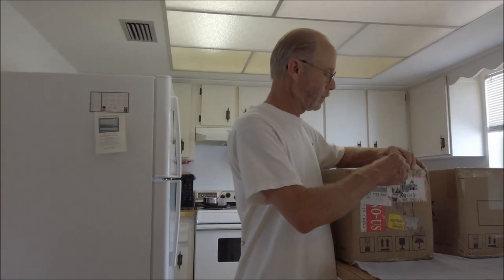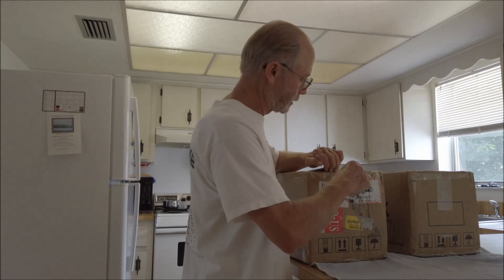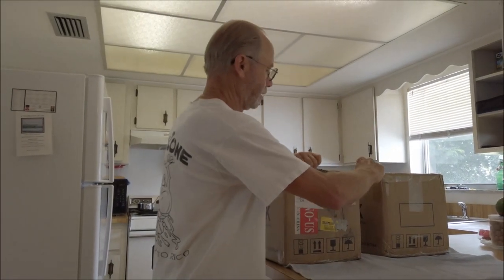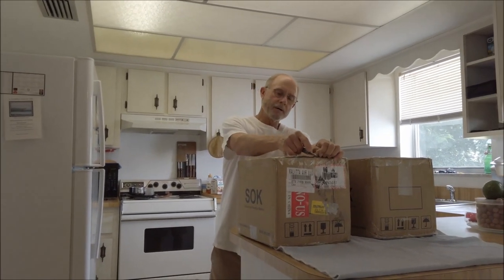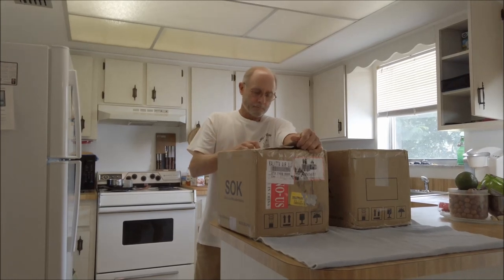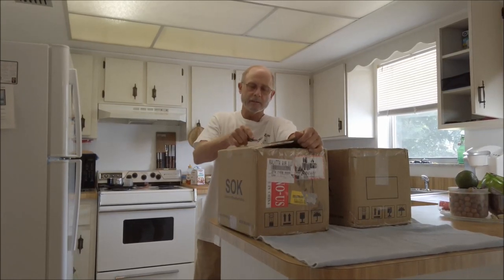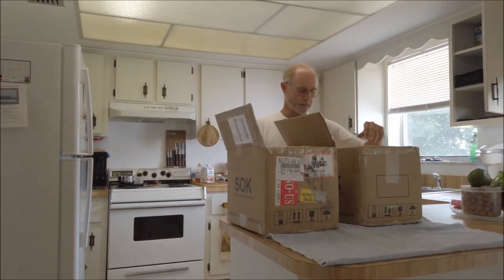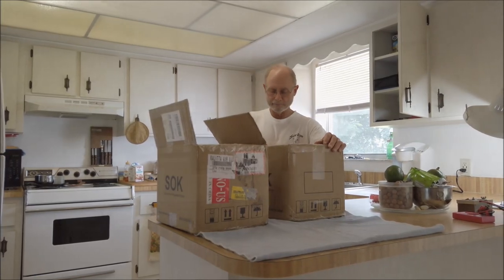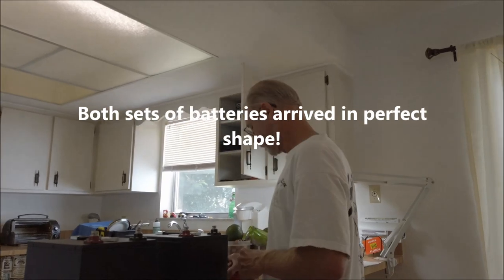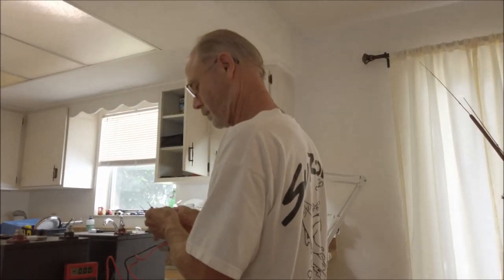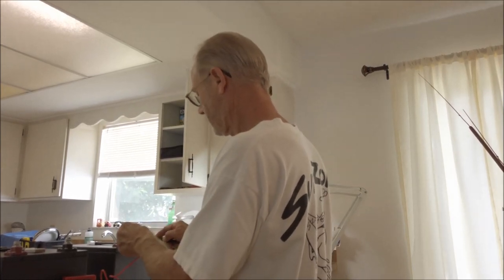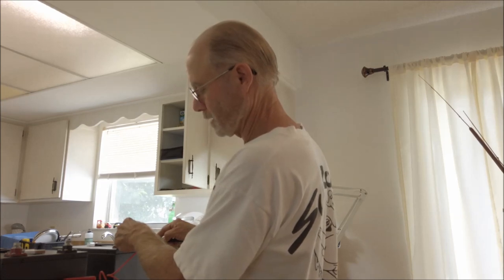And I'm going to open them up, run the camera while I do that so I can document what the condition is. They don't look too bad. The boxes are a little beat up, but coming all the way from China and then California, I would expect that they would be damaged a little bit. Everything looks good, so let's go ahead and check the voltage out. 13.36.